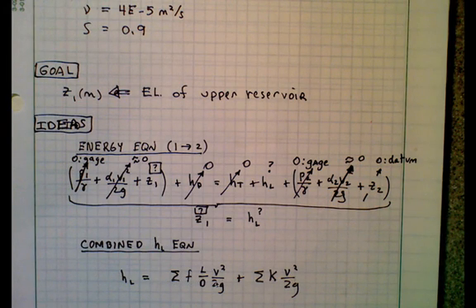This term involves head loss in the pipes, and we can look at the situation diagram and break the pipes into a number of different ones, but if we notice that they're all the same diameter, we can just simply write this as F, L over D, V squared over 2G, where L is the total length of pipe.